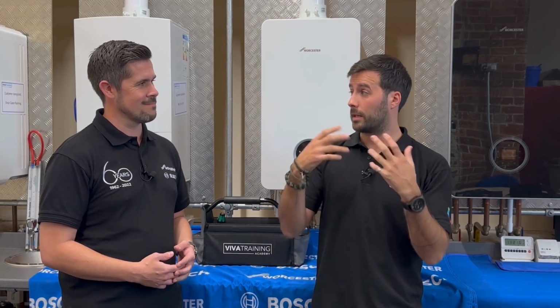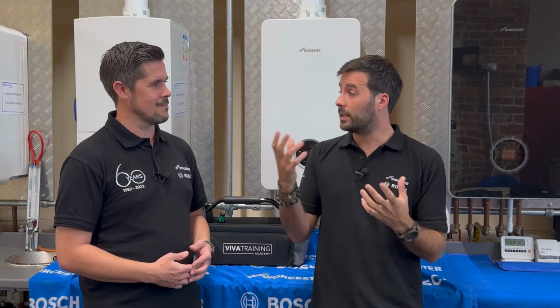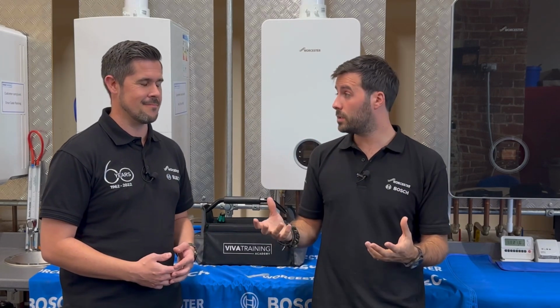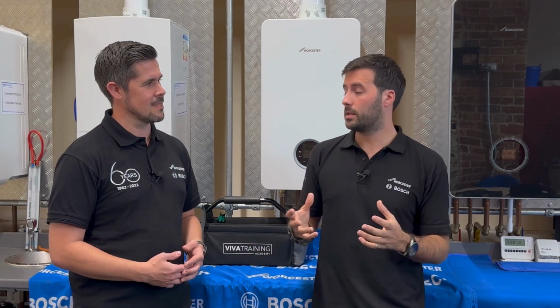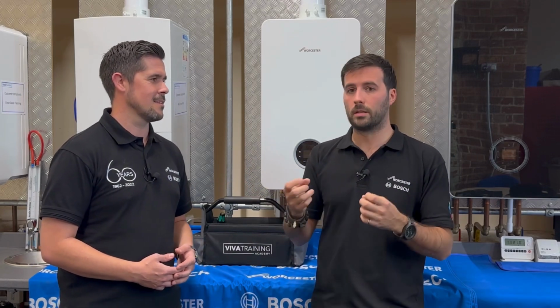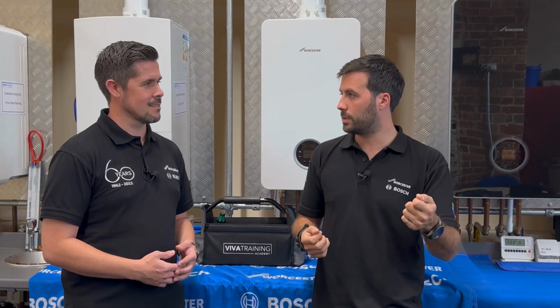Then you've got to consider, is there a problem with the burner? They can block up. Do I have to clean the heat exchanger? Has it been serviced recently? It's your basics - are the electrodes in good condition? Are they sparking? Is your rectification probe intact?